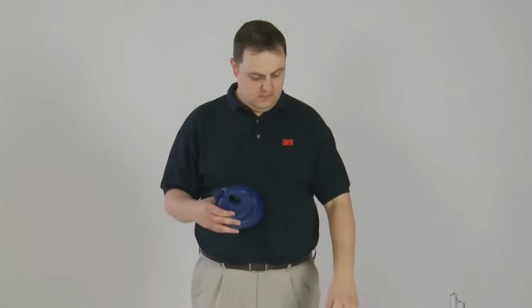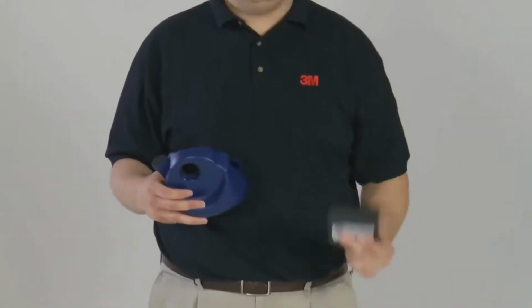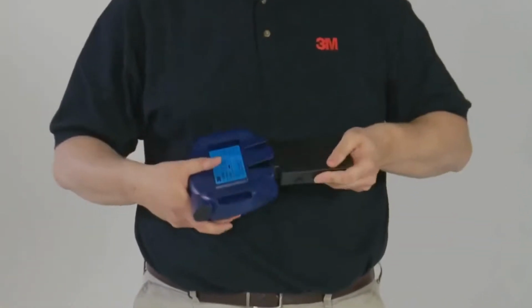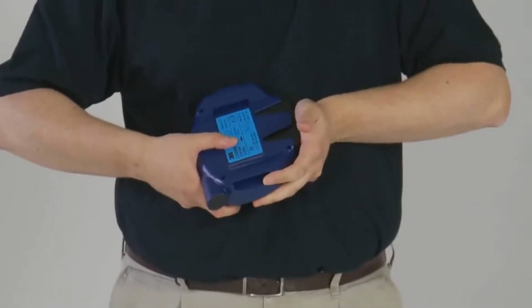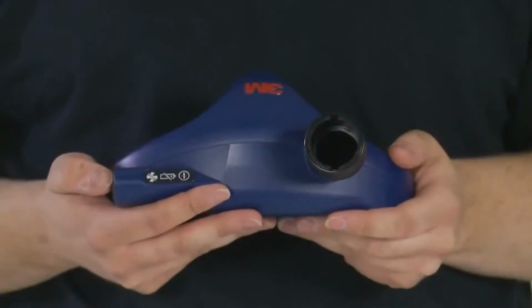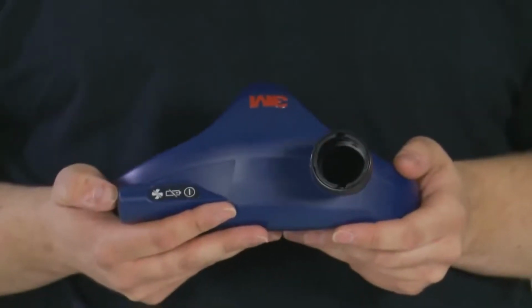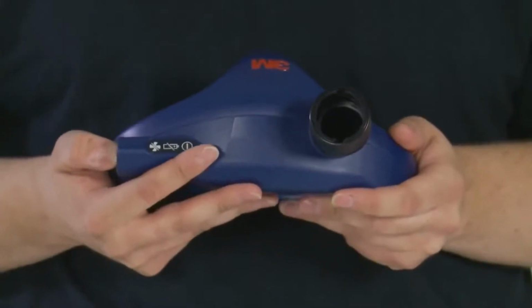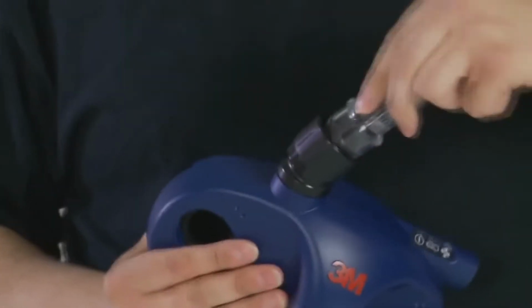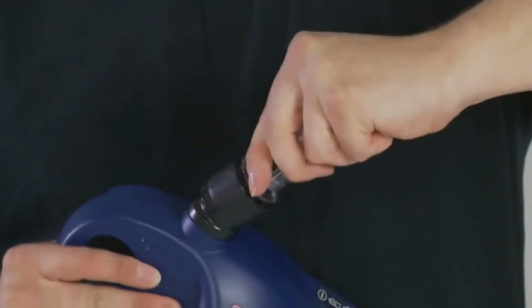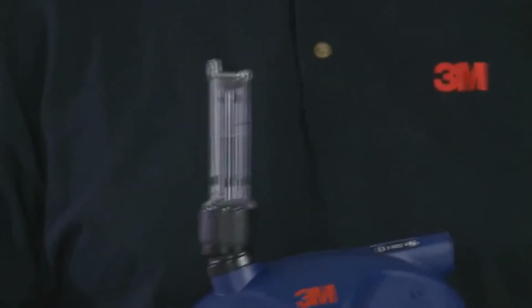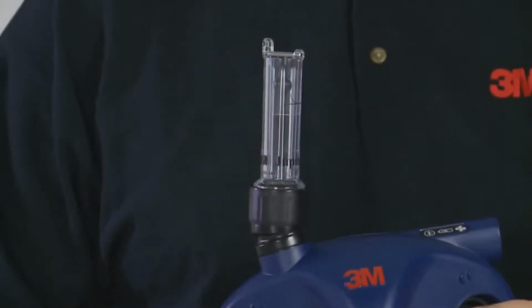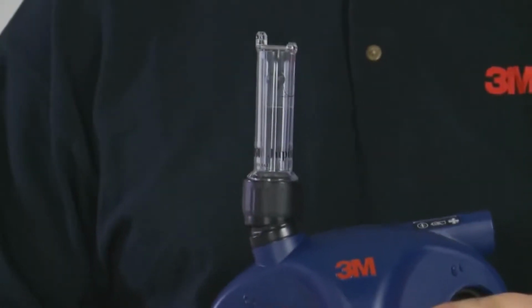Insert a fully charged battery and turn on the unit without fitting filters. The turbo should be allowed to run for approximately 10 minutes before continuing with the calibration to allow the motor to reach its operational temperature. Insert the calibration tube into the outlet of the turbo and check that the bottom of the black ball is level with the mark on the tube. If the ball is in the correct position, there is no need to recalibrate.